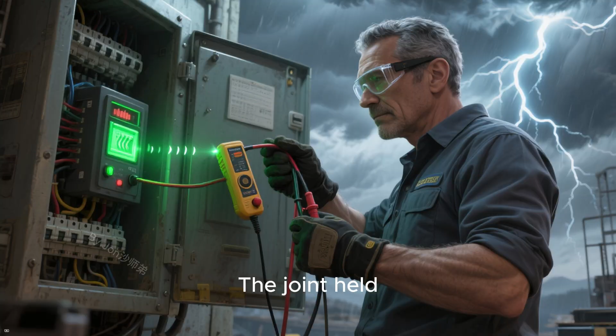He handed me a torque screwdriver and pointed to a lug. Harris: "Terminate this feeder. Correct strip length. Proper torque. Then prove it with your meter." I stripped, landed the conductor under the lug, tightened carefully to the listed torque. The continuity tester beeped clean. Harris tugged. The joint held. Harris: "Good. Loose is heat. Too tight is broken strands. Balance is safety."